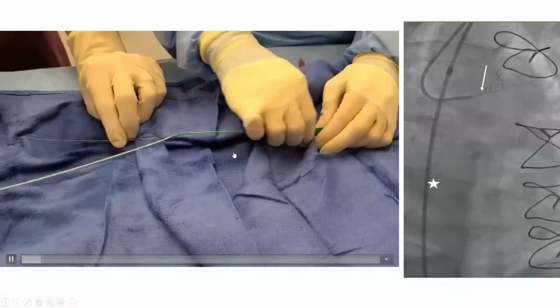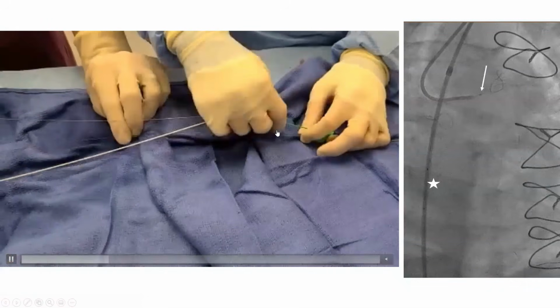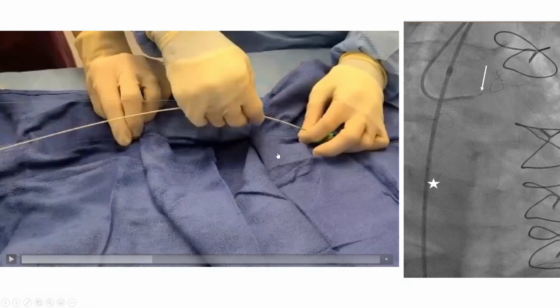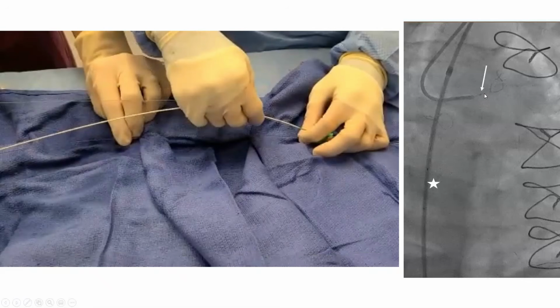Now you advance the green catheter over the BMW wire, and once you are past the BMW monorail portion, you're advancing, and now once you are over the monorail portion, you hold the BMW wire and you advance both the spider wire and the spider catheter simultaneously. Those are held in sync by your right hand, and they are pushed in sync. And as you are advancing over the BMW wire, at one point you will see the catheter tip at the tip of your guide on fluoro.